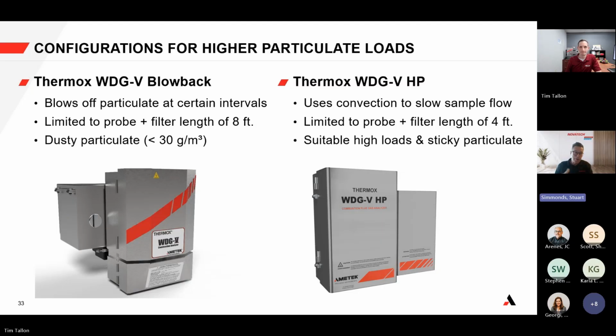So one of the things I like about Thermox is that with this fast loop concept at the bottom, we can tend to be much more open-probed for a lot of our applications, which is somewhat unusual. We're quite happy that we can handle a little bit of stuff coming in through the fast loop around the J tube and out, and then the convection loop can lift a relatively clean sample. I think that's probably the answer to why we have fewer probes on the end of a Thermox than other people do, but perhaps you could verify that.